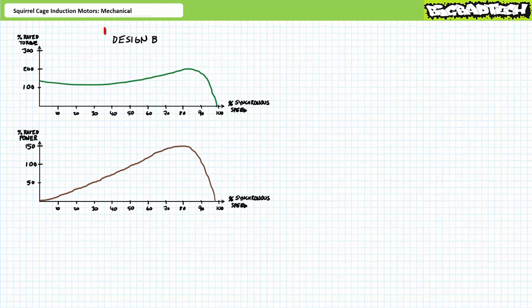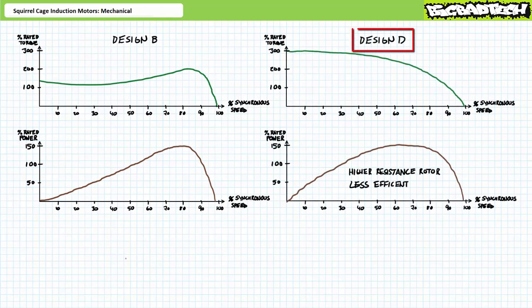The speed torque profile we examined is meant to represent a NEMA design B motor, a commonly available motor suitable for numerous applications like blowers and pumps. Other speed torque profiles exist, the second most common being a NEMA design D motor. Design D motors are designed for high inertia starts like a crane or a hoist. As evidenced by the speed torque curve, design D motors produce higher torque at lower speeds.